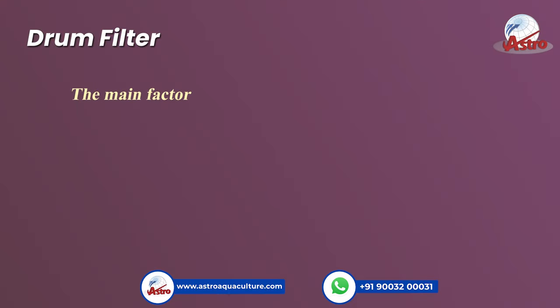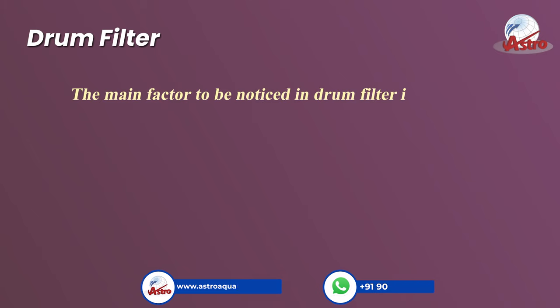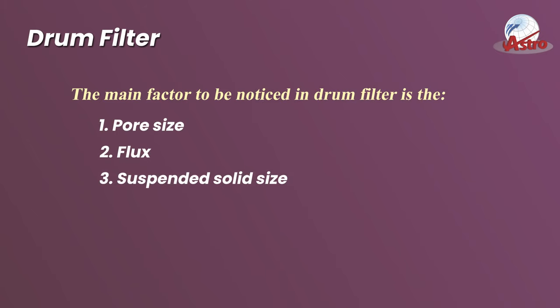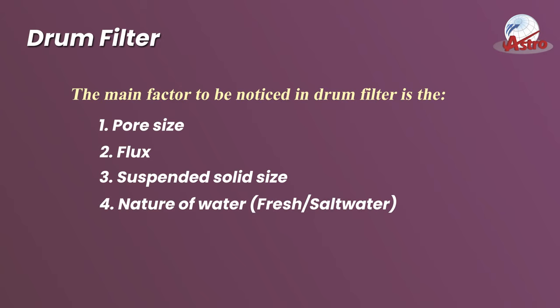The main factors to be noticed in a drum filter are the pore size, flux, suspended solid size, and the nature of the water — whether it is fresh or salt water.